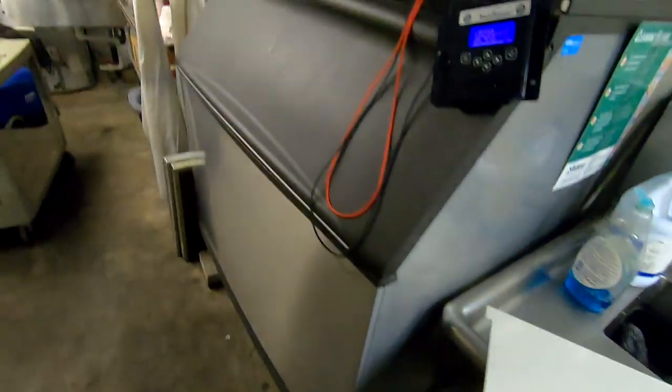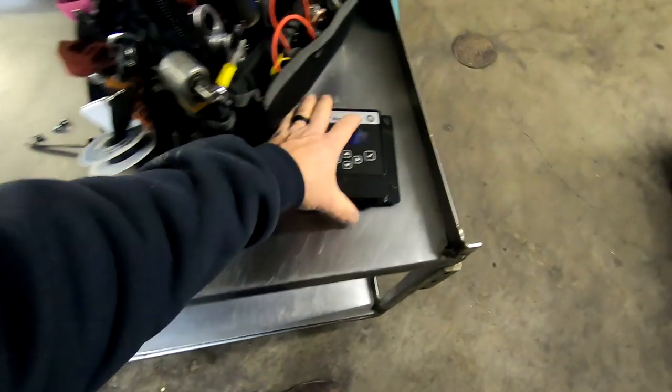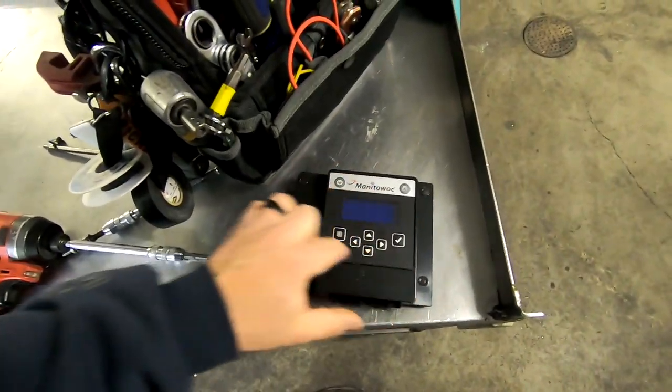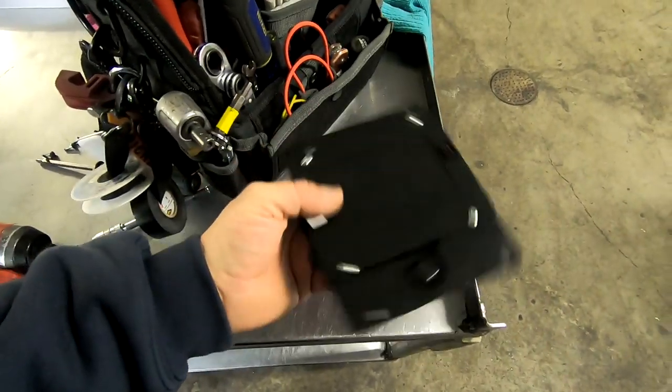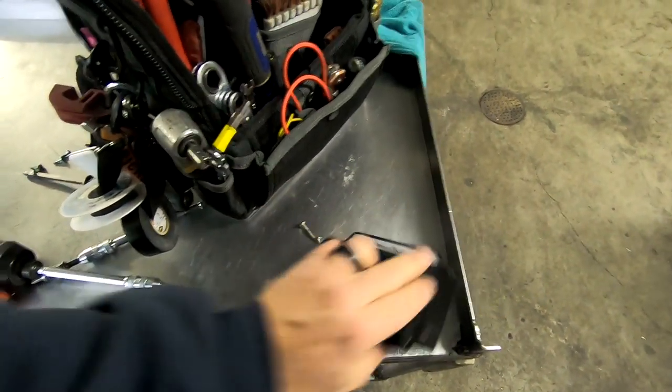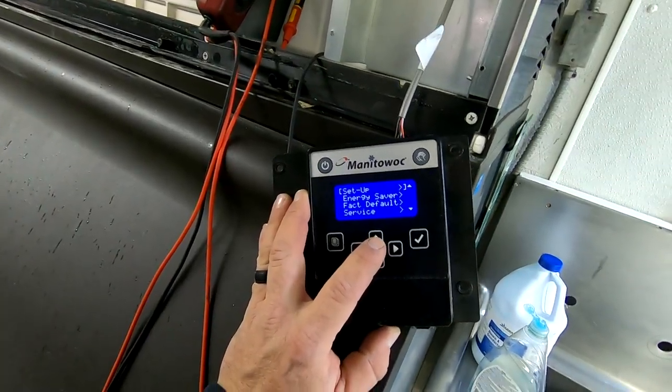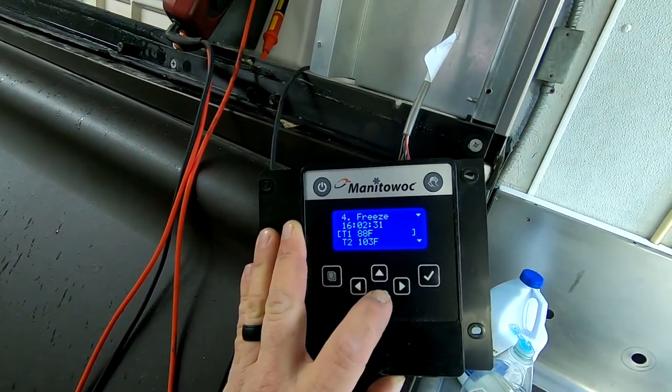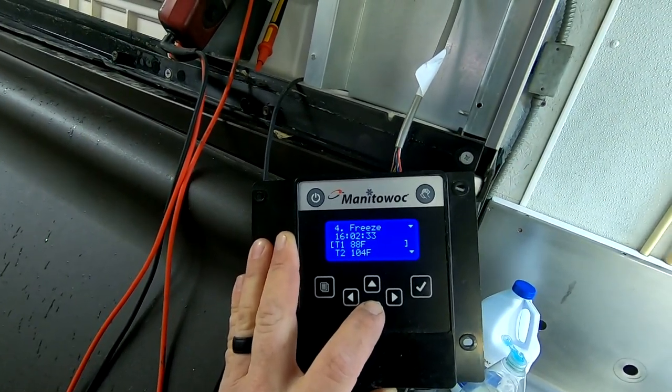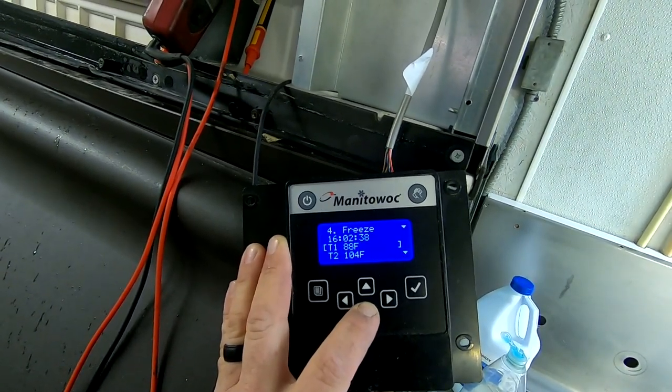Otherwise you might lose some of your water over the front. Likely what's going on with this is the keypad here is bad, and you can replace just the keypad and not the control board, which is a lot cheaper than a whole control board. So we'll order that. Let's see what our temperatures are doing, running about 102 discharge gas.